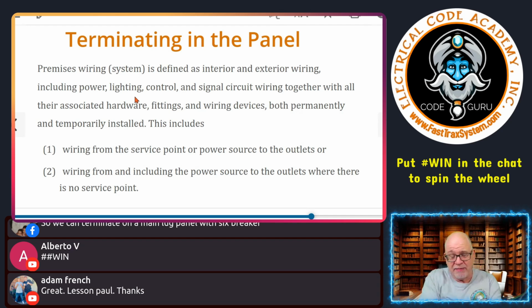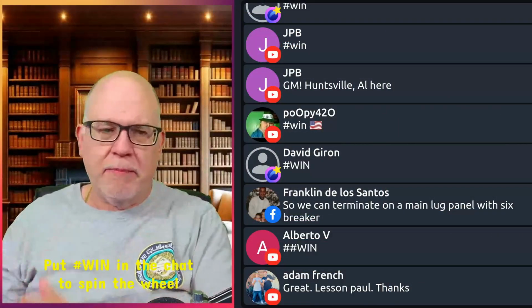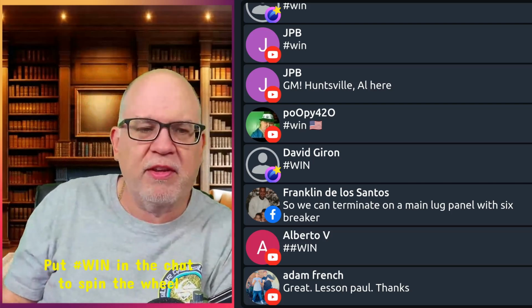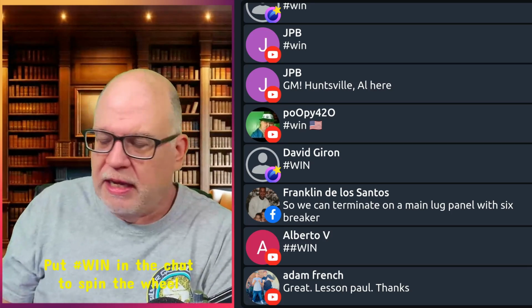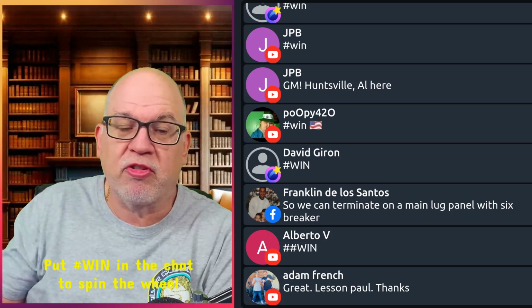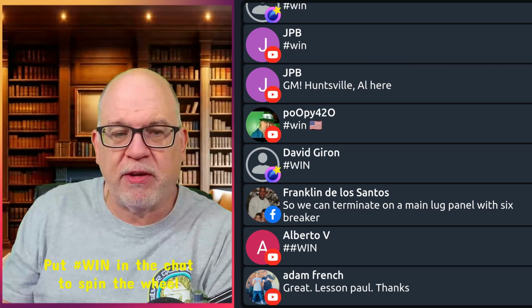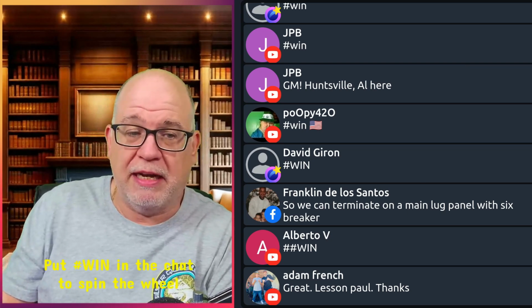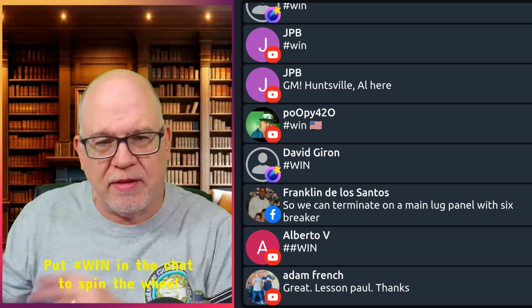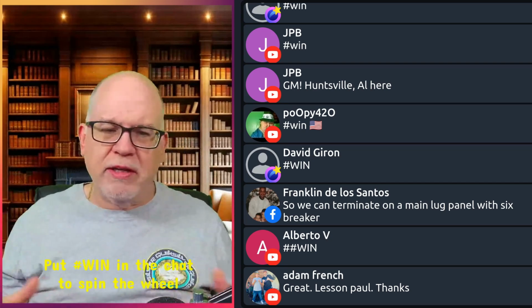That's another thing that people lose sight of all the time. They think when you do something temporary that you still don't have to follow the code. You most certainly do. One of the biggest things I get from people all the time, not to deviate away from the discussion, is temporary poles, services for temporary job site construction. So many people think, and maybe your jurisdiction allows it, that if I'm going to be driving ground rods, I only need to drive one because it's temporary. It says that nowhere in the code.